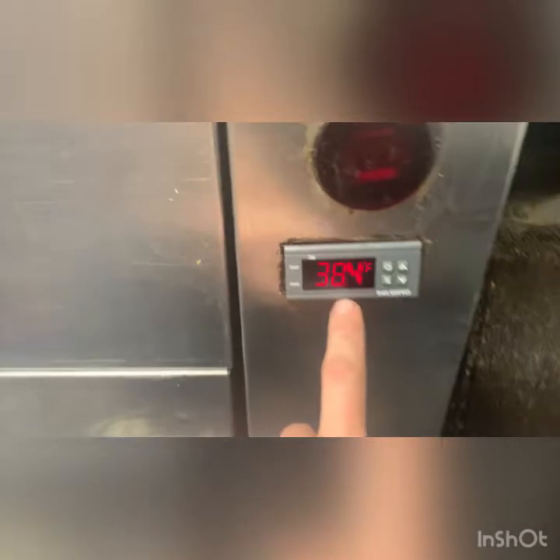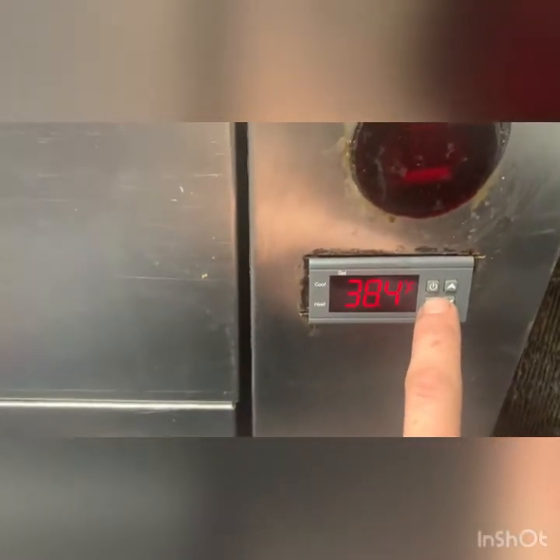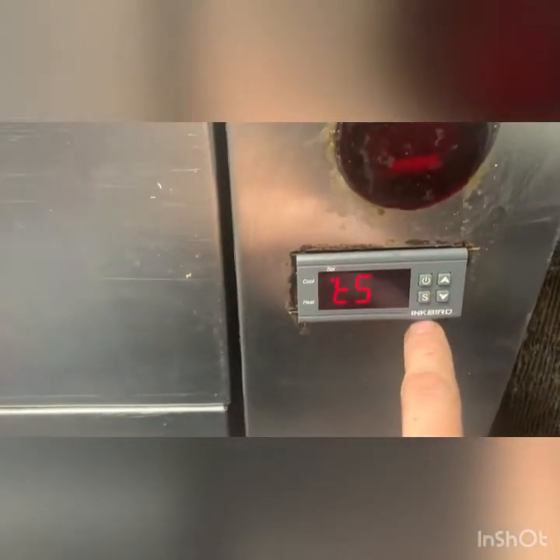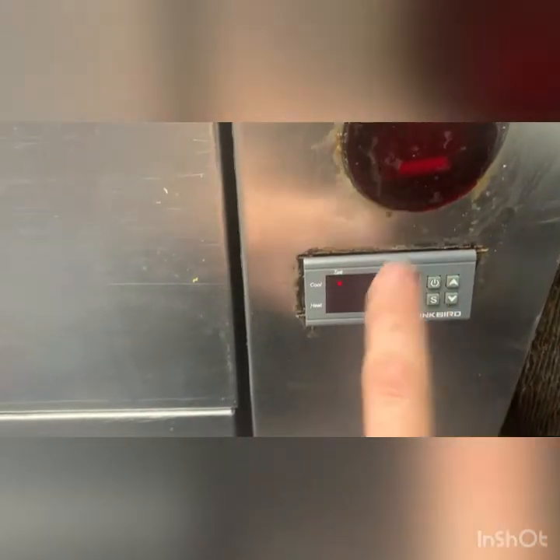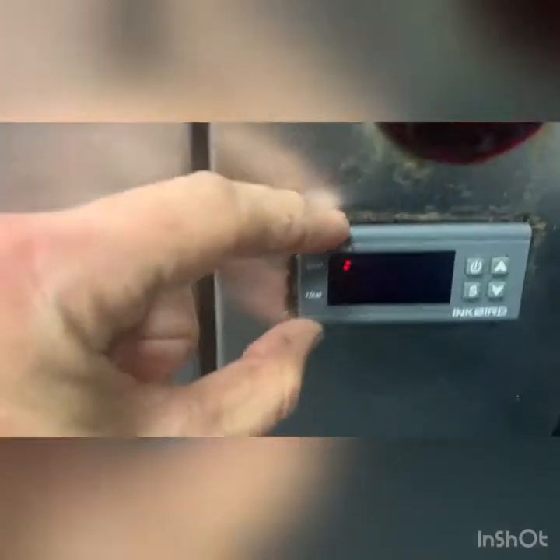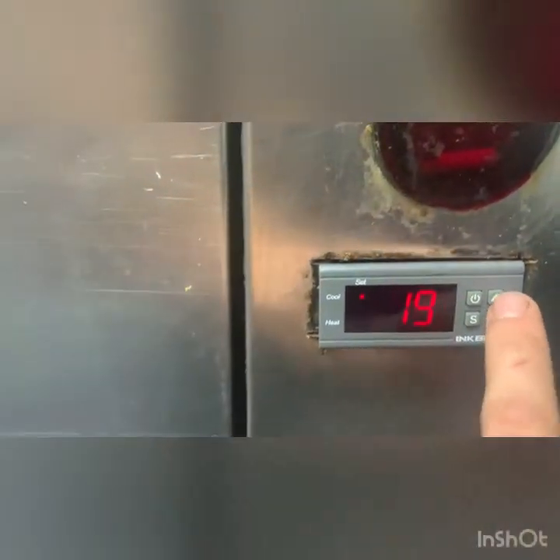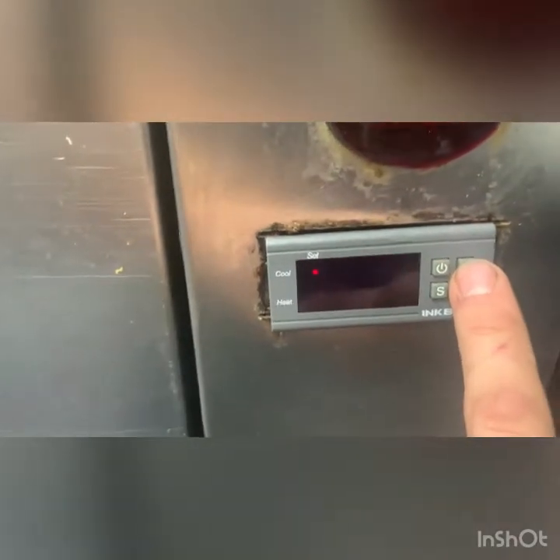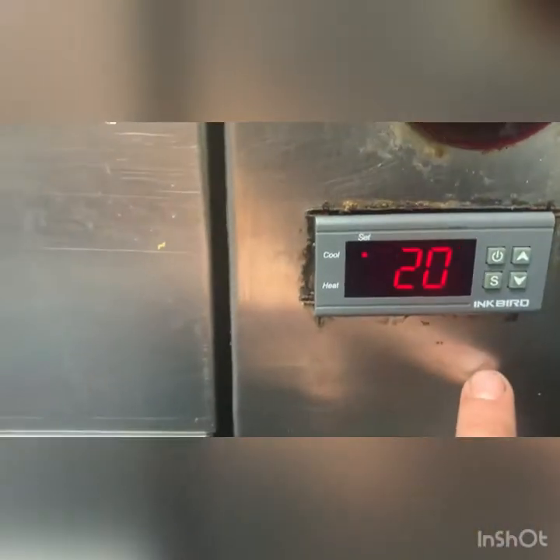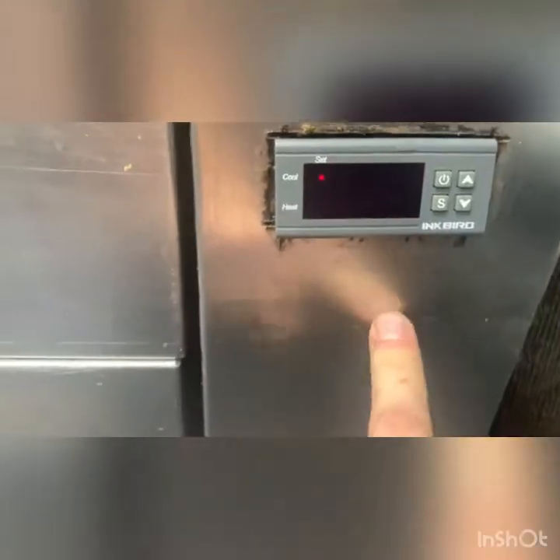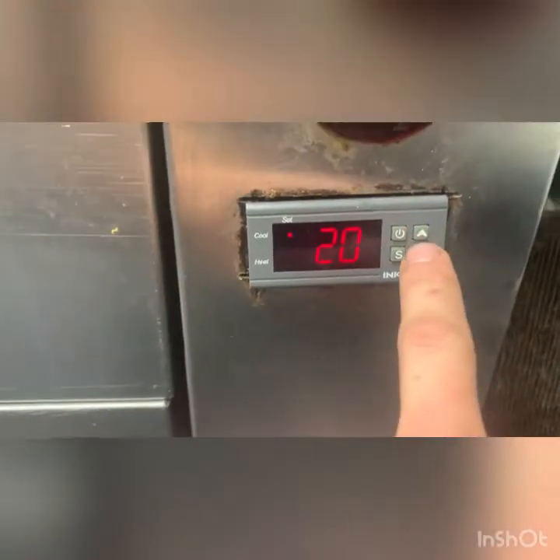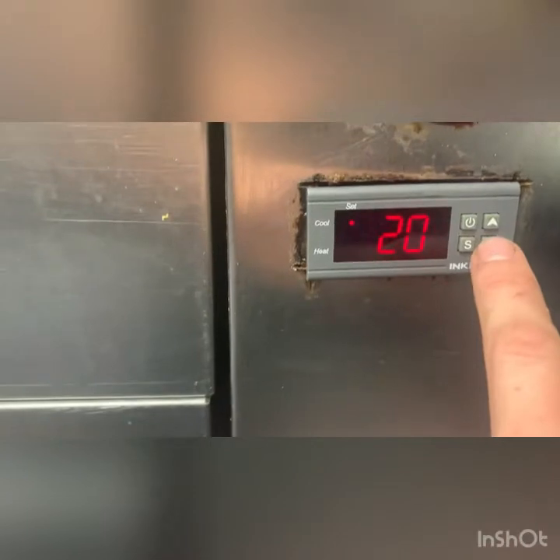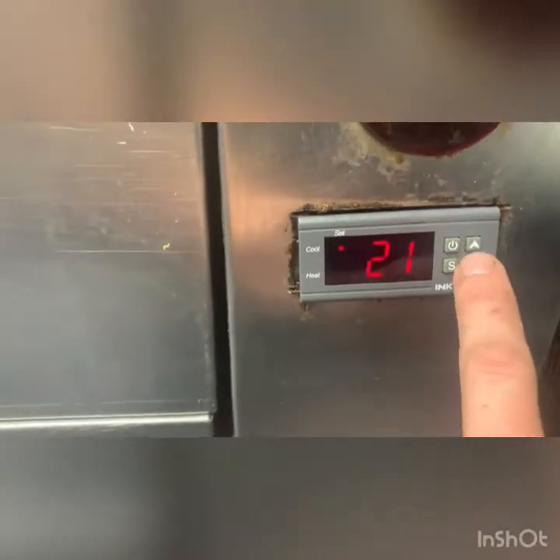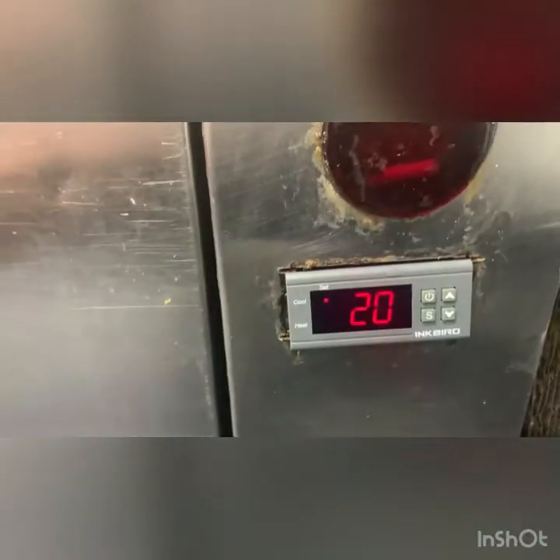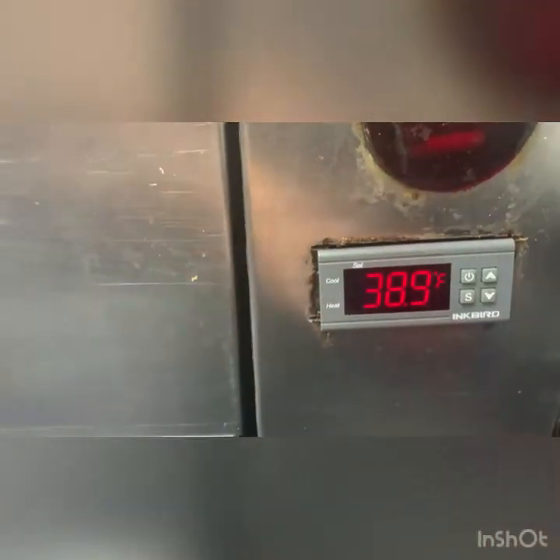All right, let me go over the settings of this. As we hold this down, temperature setting, right? Okay, this is set for 20. On coolers, generally speaking, your sensor isn't an air temperature sensor. It is a coil temperature sensor. So the compressor's running, the coil's getting colder and colder. And we've just played with the numbers to find out that when the coil is about 20, the box is about 33. And so that's what we want. So we're going to set that.